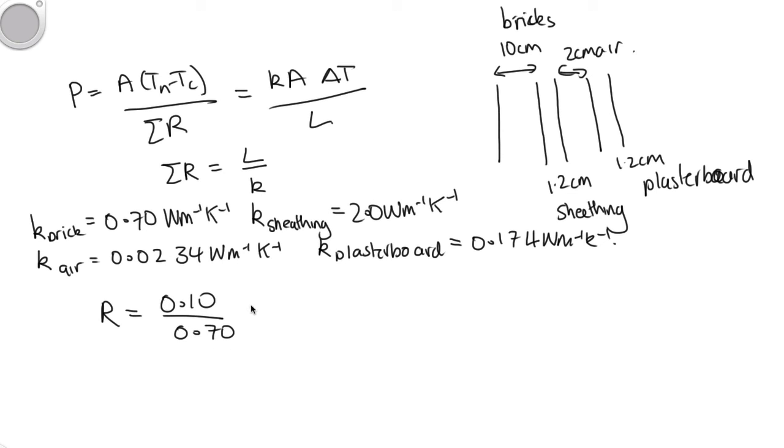So R total is equal to 0.10 meters over 0.70 plus we've got the sheathing, so that's 0.012 meters over 2.0, plus the air, which is 0.02 over 0.0234, plus the plasterboard, which is 0.012 over 0.174.